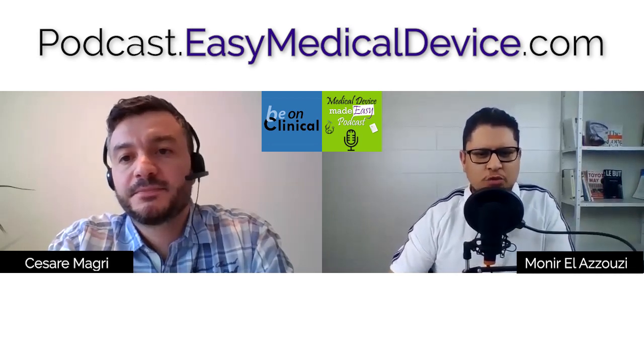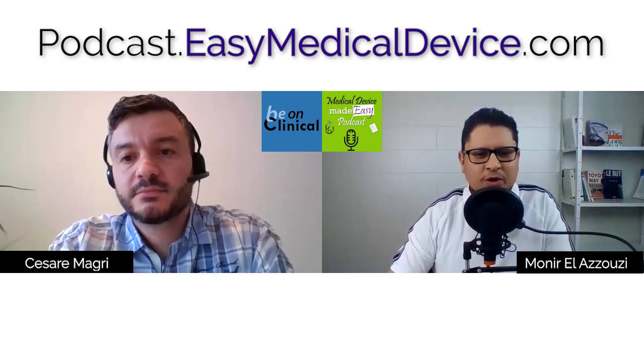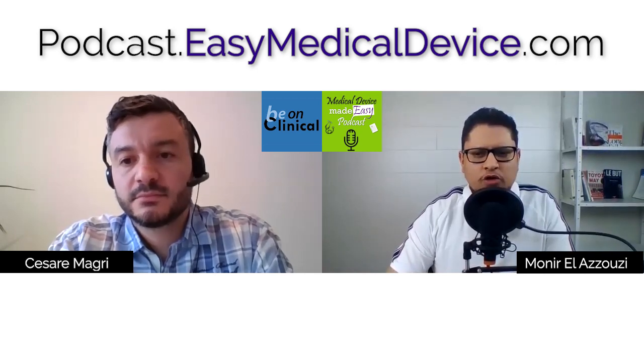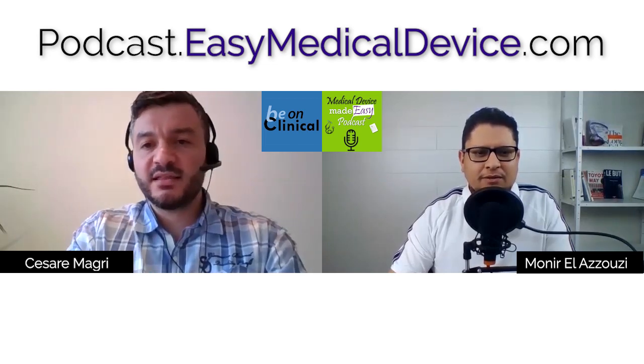It's really showing what the limits are, what is exactly inside and what is outside, which, as I've said, can clarify why we are using it, how we are using it, who should use it, etc. I think it's the main question that we are asking. We should ask those questions ourselves, and the answer should be in the intended purpose, so that you can be clear on your product. And note that in the intended purpose, except in some cases where you're referring to a specific class of well-known devices, you don't even have to mention the solution that you provide. Up to this step, we didn't say how the device achieves its goal.